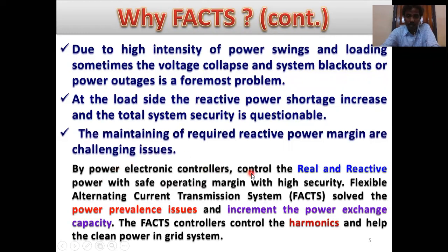By power electronics controllers, we control the real and reactive power with safe operating margin and high security. Flexible alternating current transmission systems solve the power imbalance issues and increase the power exchange capacity. The FACTS controller controls the harmonics and helps provide clean power in grid systems. This controller also controls sag, swell, flicker, and any type of power quality issues. These can be handled.